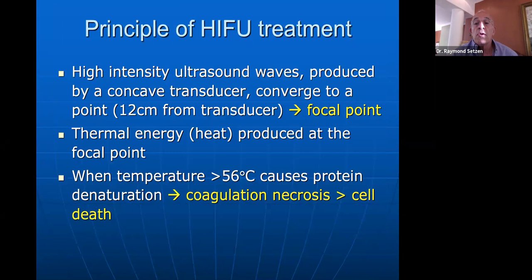When we look at the principle of HIFU treatment: high-intensity ultrasound waves are produced by a concave transducer, a ceramic piezoelectric transducer. Because it's concave in shape, all the ultrasound waves converge to a focal point, which is 12 centimeters from the transducer. At that focal point, thermal energy is produced, and when the temperature reaches greater than about 56 degrees Celsius, it causes protein denaturation, which leads to coagulation necrosis and cell death.